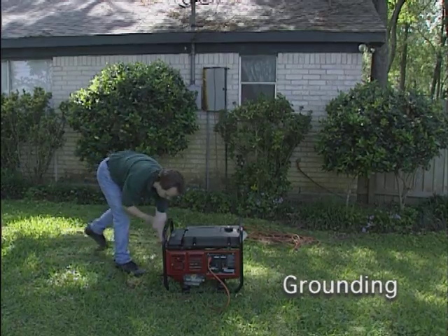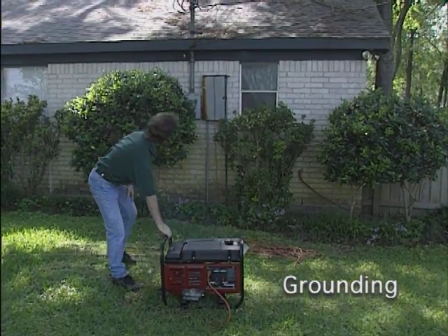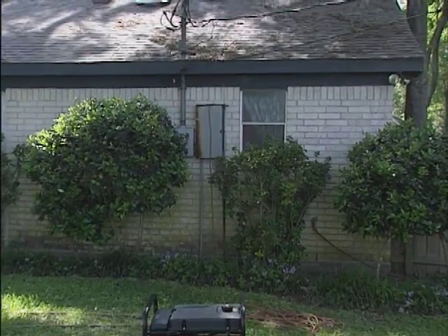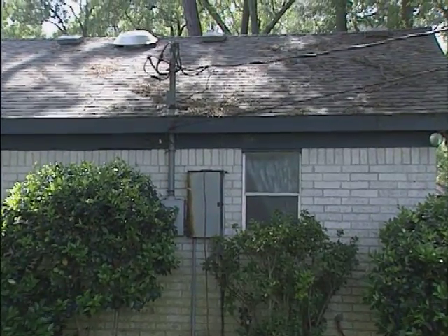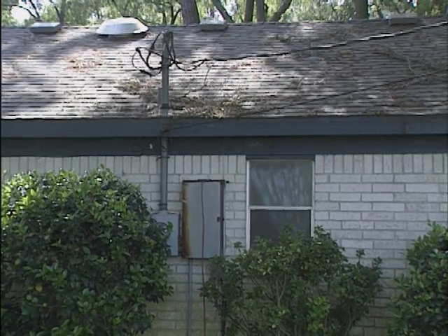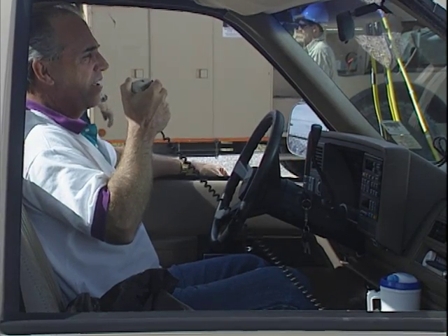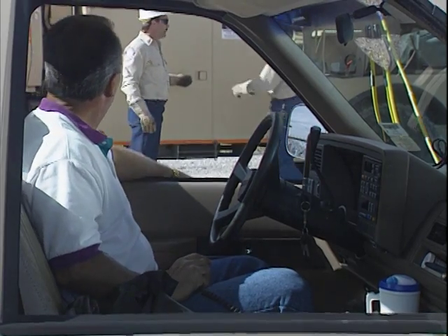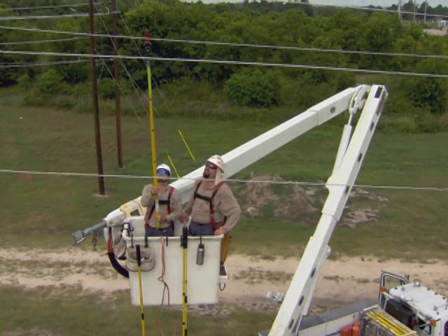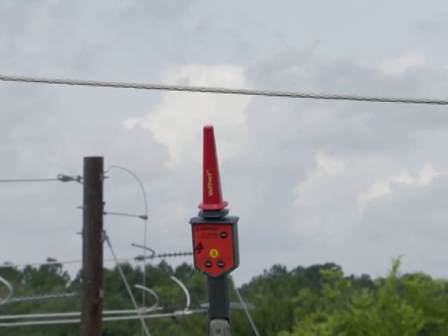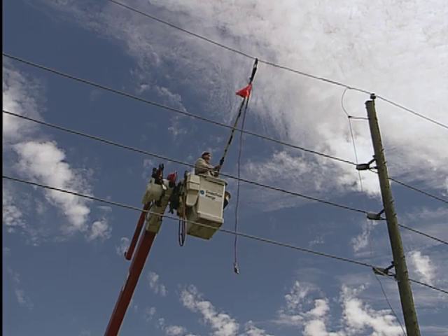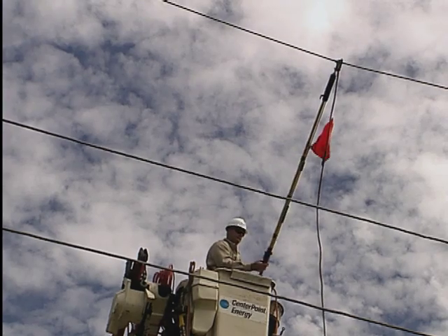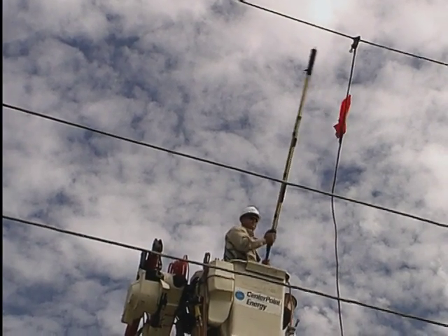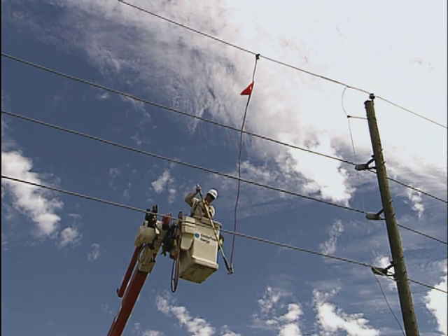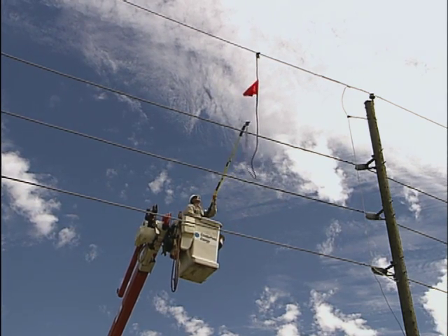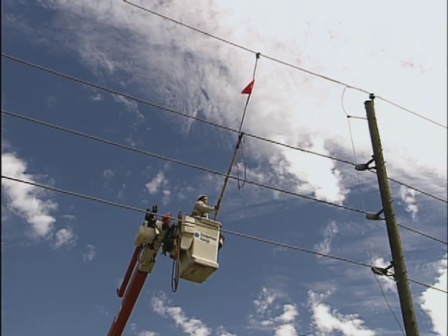Backfeed from generators or other customer-owned equipment is common during long-term outages. For your protection, all work on de-energized conductors and equipment must be done between grounds. Your coordinator will arrange a clearance before grounding sections of feeder circuits. To ensure safety, test the equipment and conductors to make sure they are de-energized before grounding. Available fault currents on our distribution system dictate the use of 2-aught copper grounds. Once the lines are grounded, place an orange flag and a tag with crew leader's name and phone number at the site so grounding locations and crew can be readily identified.